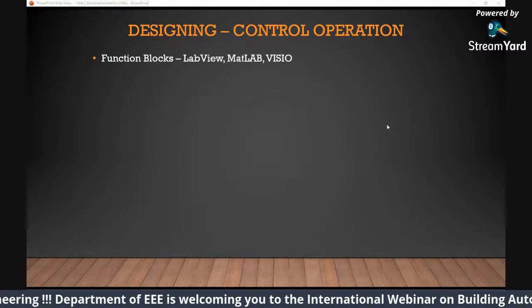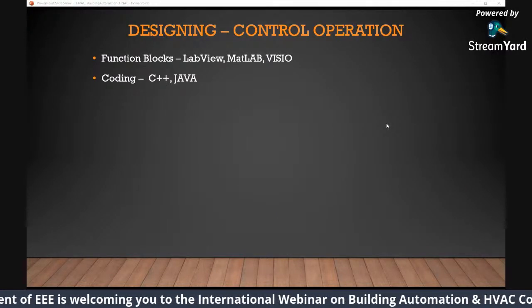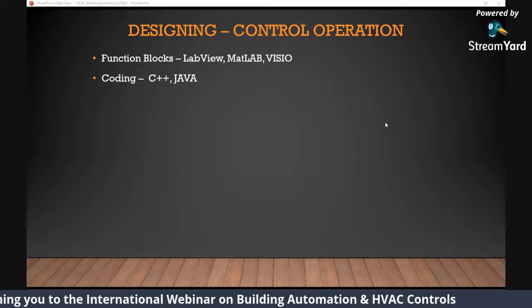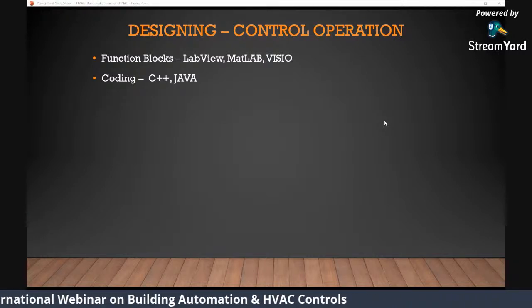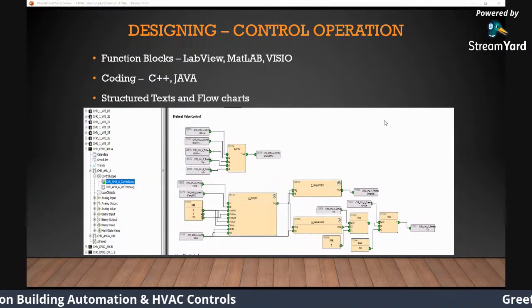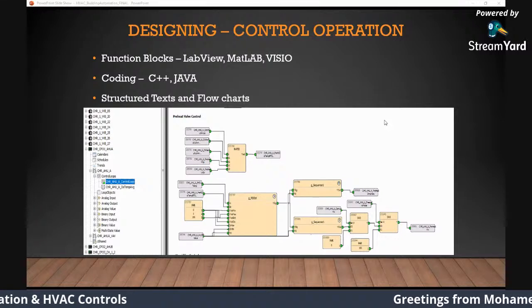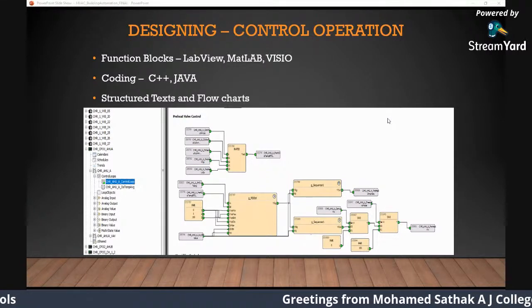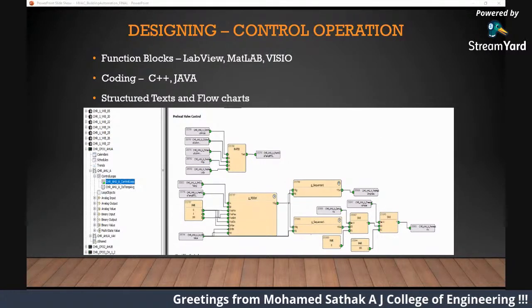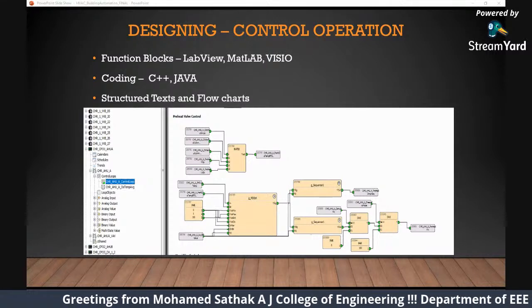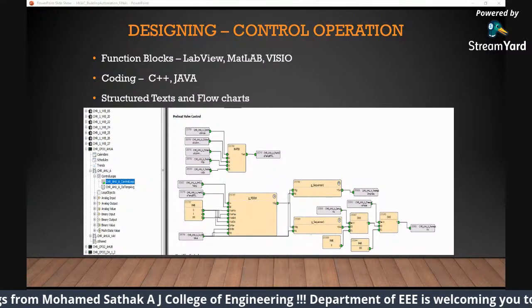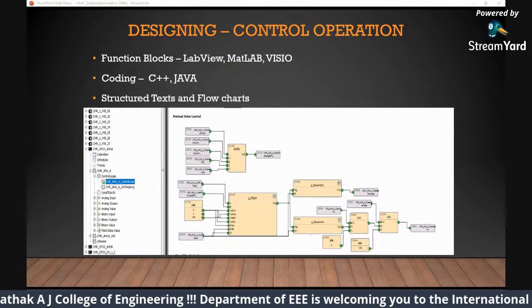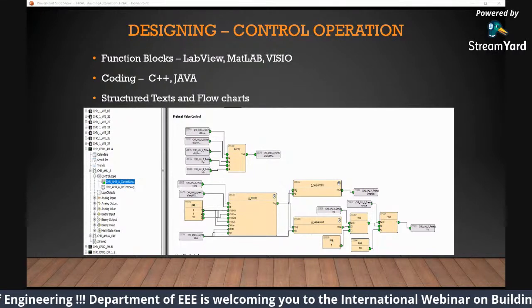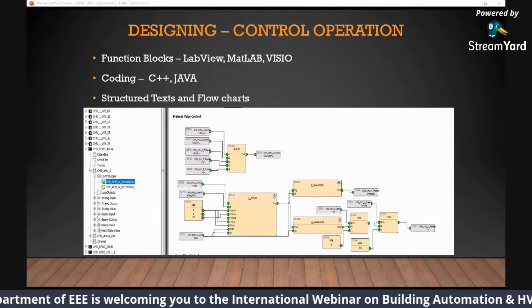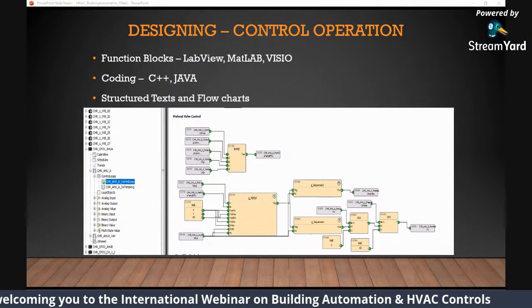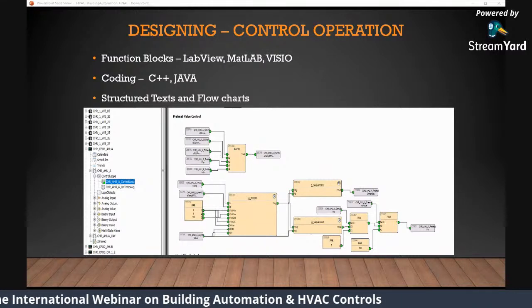All right. So we have dealt with all your electronic equipment, controllers, sensors, output devices. How do we design it? Okay, so this is one typical example. This is how we design. Your controller is the brain of your building automation system. It will command, like you're controlling or monitoring things. It will say what to run, what not to run, what to turn on. It will say if the damper has to open, if the fan has to turn on. It does it automatically.